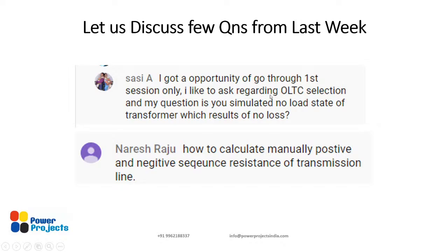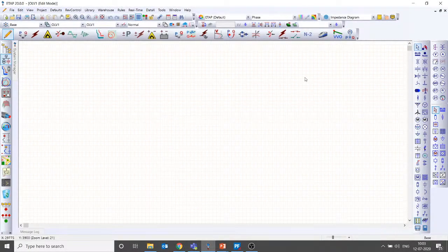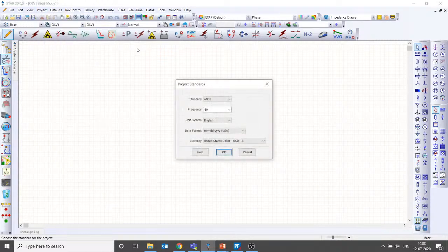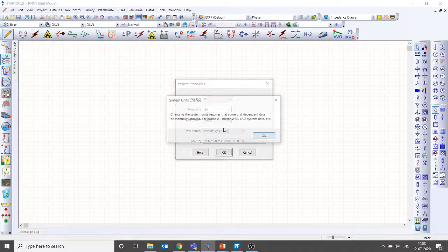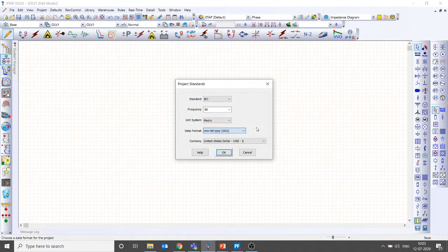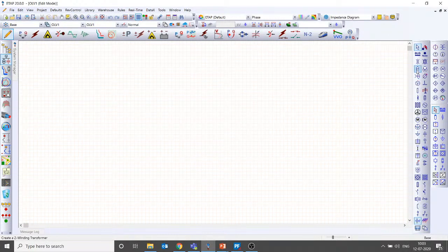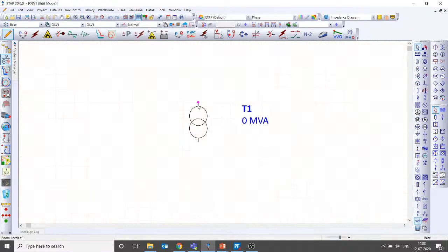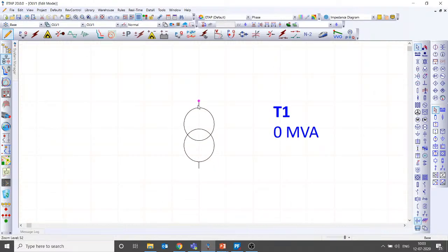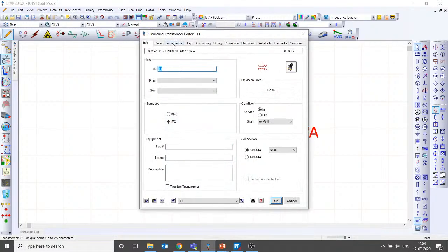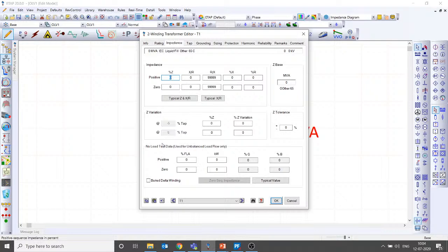I believe I added a little introduction about it last week, but let me talk a bit more on this. To ensure, I am starting the project with IEC standard and 50 Hertz. If you look at this transformer ETAP modeling, it takes only the load loss into account for a load flow analysis, and only for an unbalanced load flow does it take the no load loss.